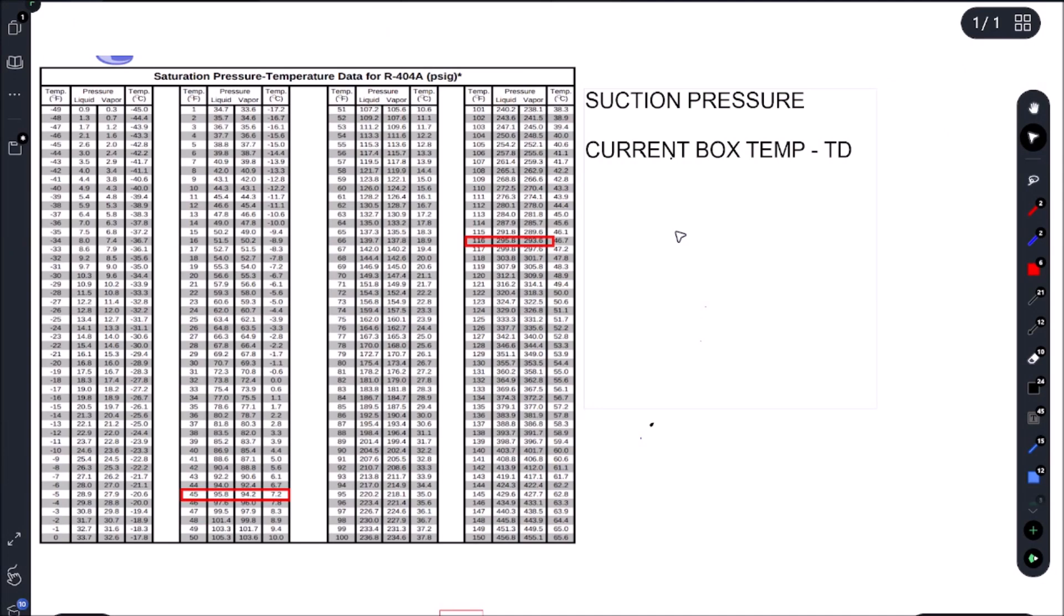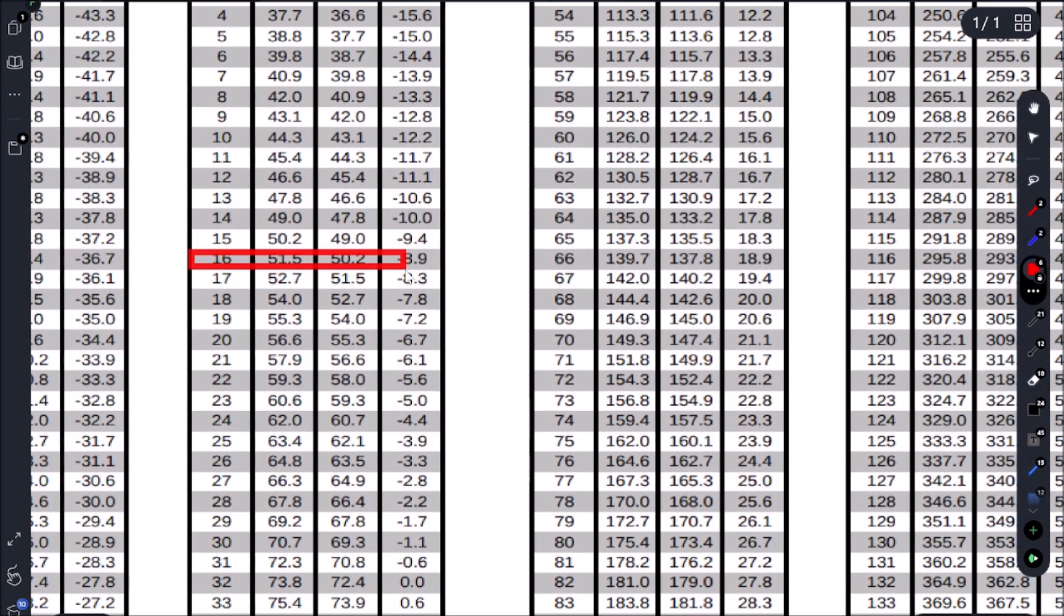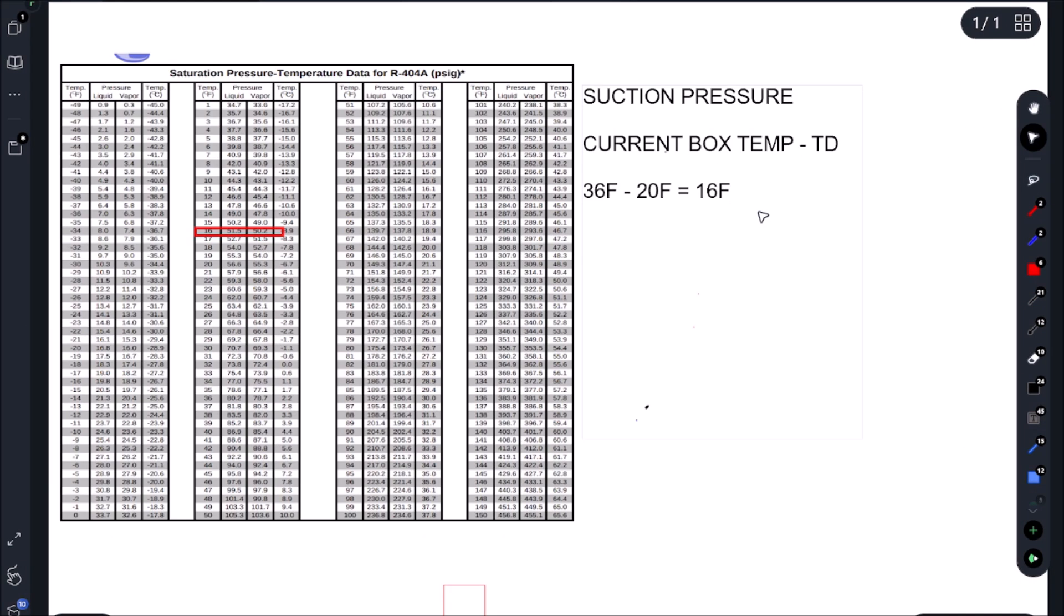So let's go see if our pressures are correct. Just because the site glass is clear doesn't mean things are correct. We could have low suction. We could be frosting up this coil. So we ended up with 36 Fahrenheit. And to find out what our pressures need to be we subtract our EVAP TD. So that gives us 16 Fahrenheit. And 16 Fahrenheit gives us about 50 PSI. And we had 52 PSI.